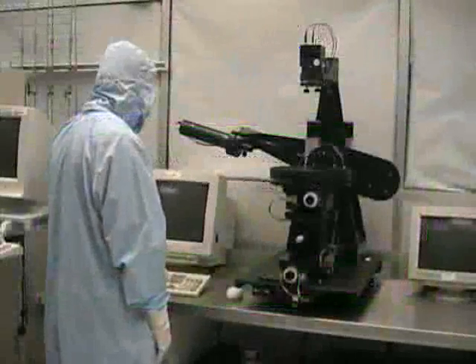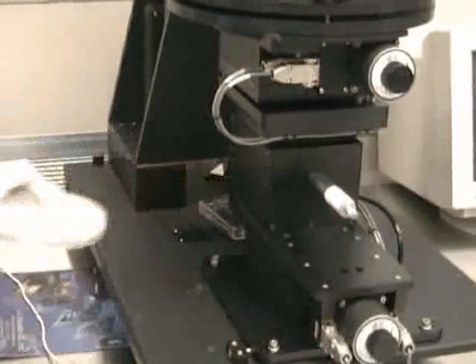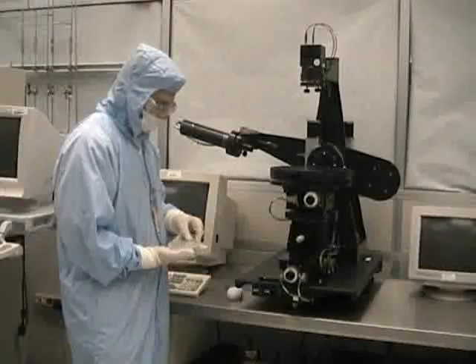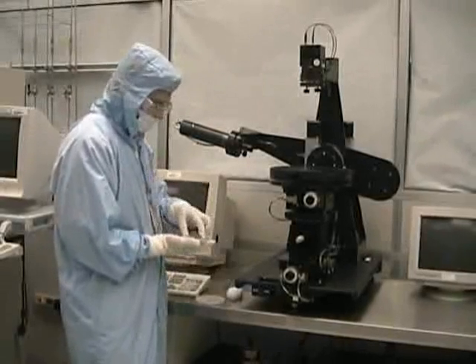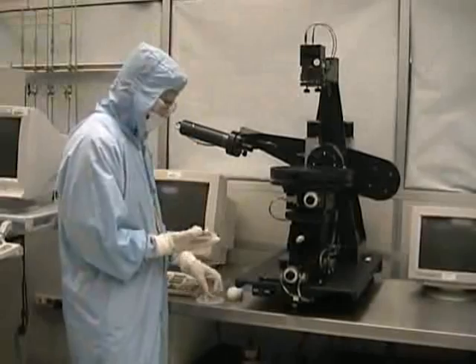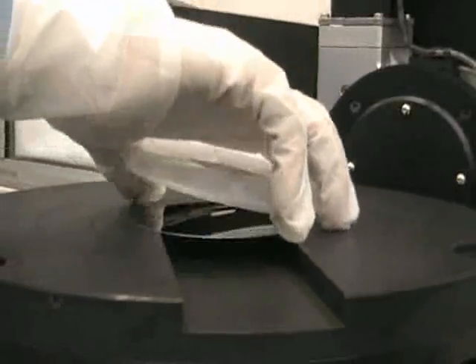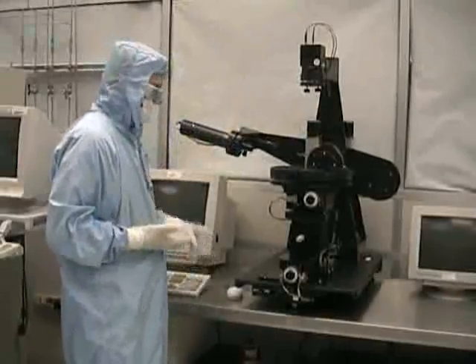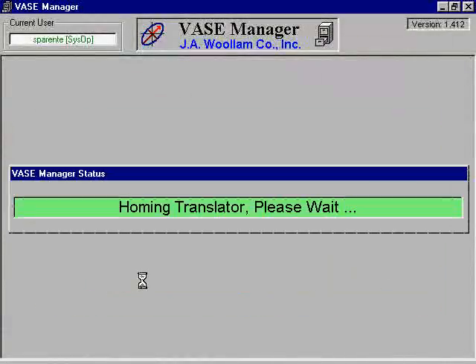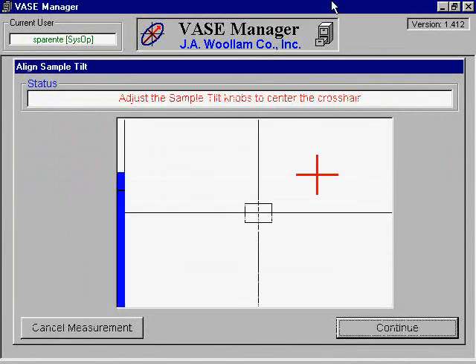The system will prompt you to mount the calibration wafer onto the sample stage. The calibration wafer should be in close proximity to the ellipsometer and is clearly marked. Follow the on-screen instructions. Setting up the calibration wafer for a scan consists of the same basic steps as a normal scan.